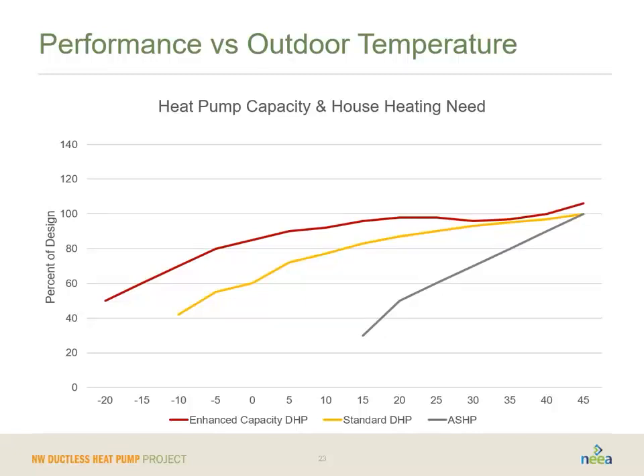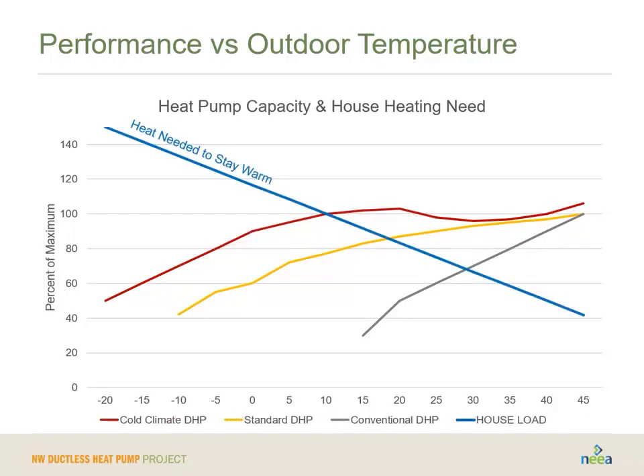So let's take a look at what can be achieved by the heat pump and what would have to be made up by the other heat in the home. If you have a standard air source heat pump, and this is how much heat the house needs to stay warm, the conventional heat pump is going to match around 30 degrees, maybe a little bit below that. It's able to produce exactly as much heat as is needed to keep the house warm. So what happens below 30 degrees? How do you keep the house warm with the standard air source heat pump?